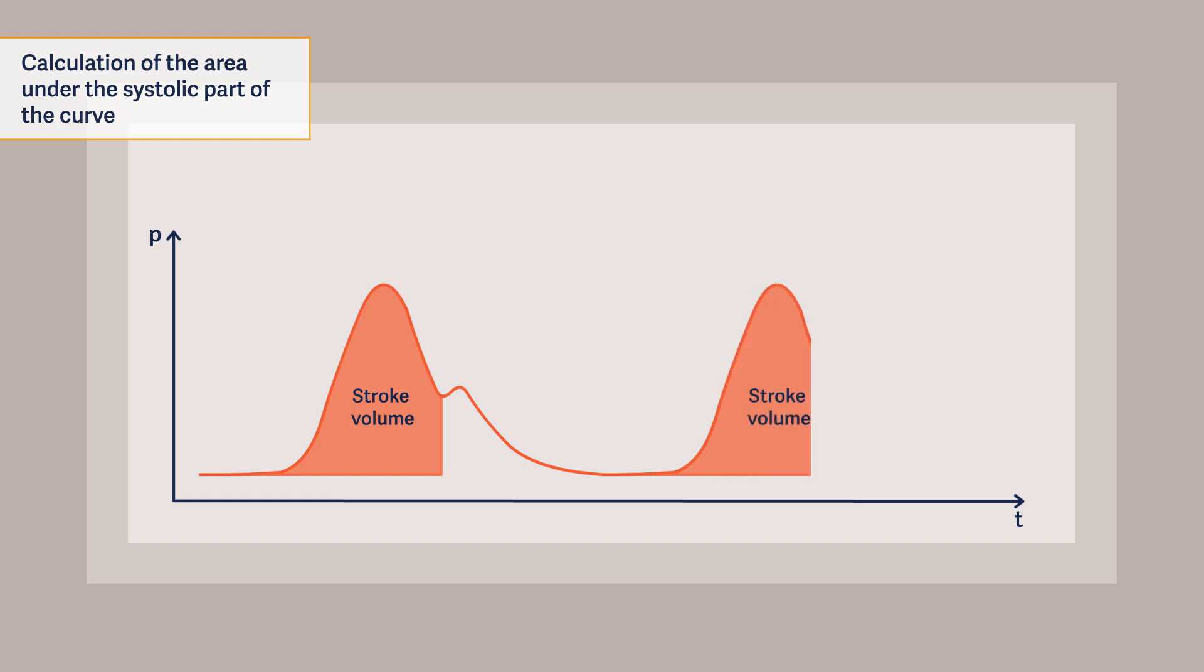The Pulse Contour analysis involves continuous analysis of the derived arterial pressure signal. In the first step, it determines the area under the systolic part of the curve, which reflects the stroke volume. By multiplying the stroke volume with the heart rate, a continuous beat-to-beat cardiac index, or CI, is determined.